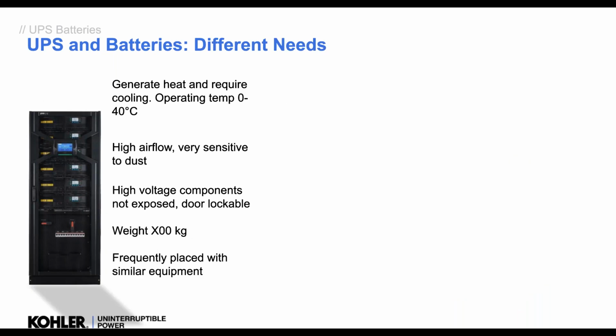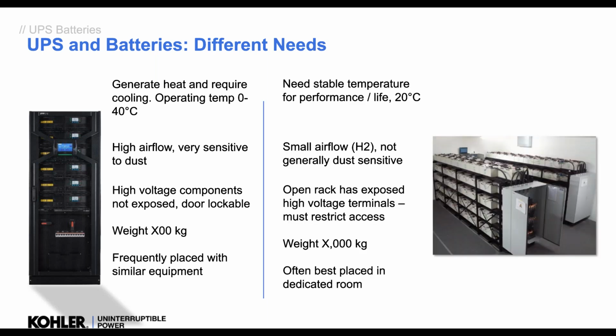All right. So we've seen that UPSs and batteries have different needs. Typically, the UPS can operate in a variable temperature, typically 0 to 40, but the closer we keep it to 20 to 25, the better. They're sensitive to dust. We shouldn't be in a dirty, horrible environment. We should be in a clean environment. Everything's safe, we're locked behind the door. Typically the weight is 100 kilos or upwards, and typically we put that in with similar equipment.